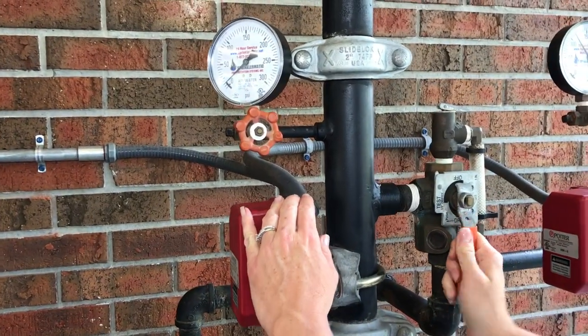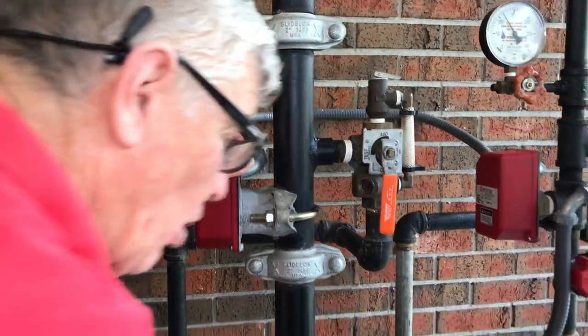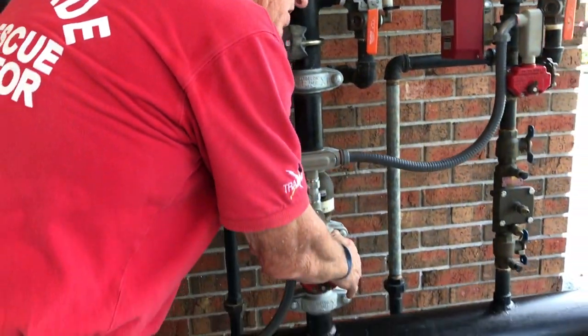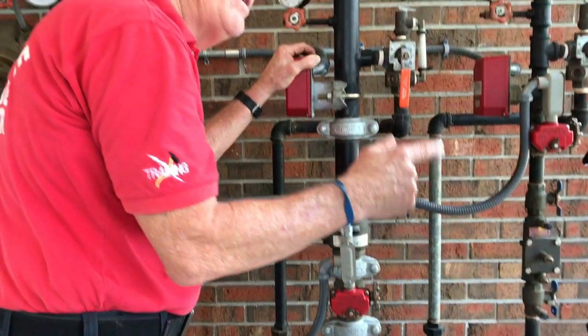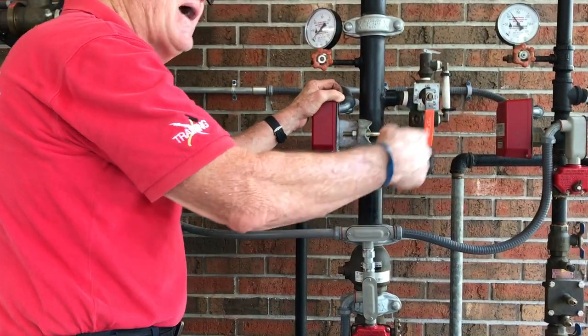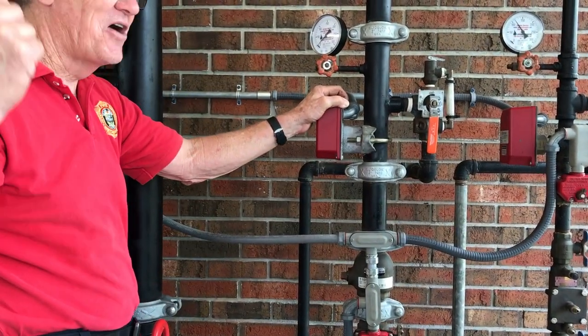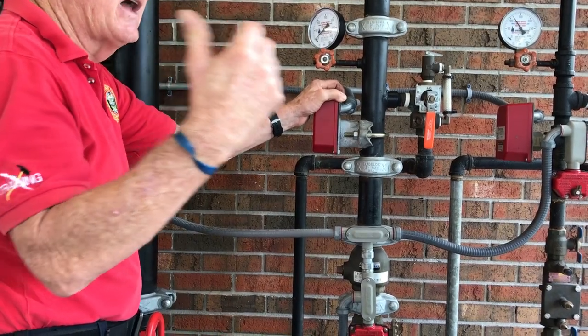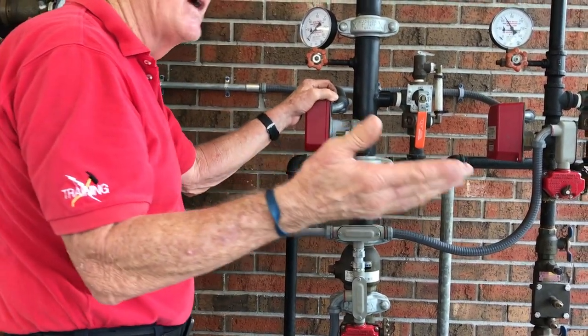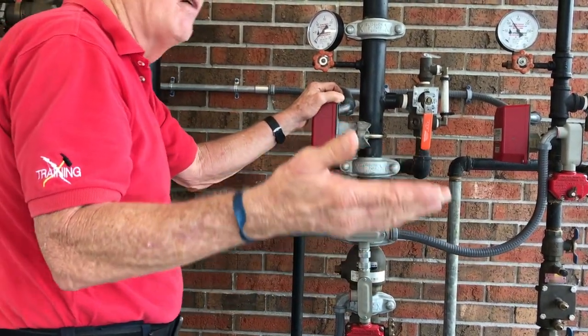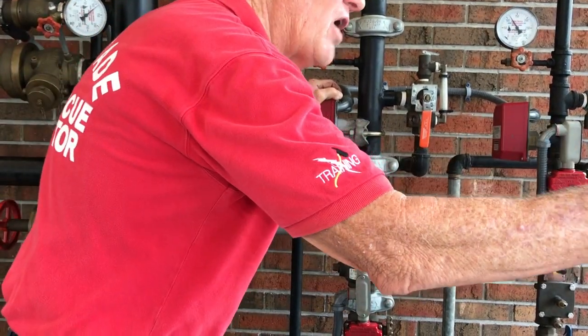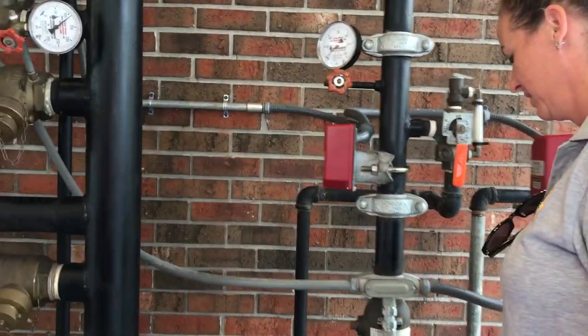Very good. And we're going to slowly open this valve because if we open it too fast, we may exceed the capacity of the jockey pump and start the diesel fire pump. And if that happened, we'd have to write you up and suspend you, probably give you about 2 weeks off, okay? But I don't want to make you nervous, all right? Okay, go ahead, open it back up.